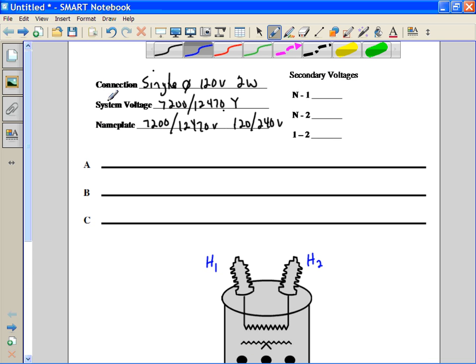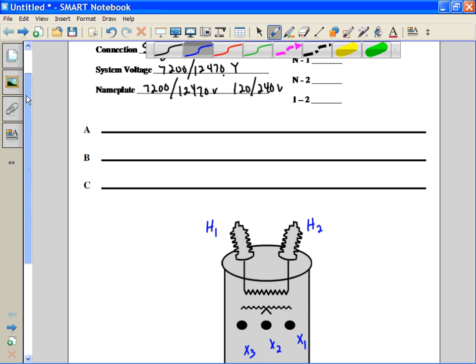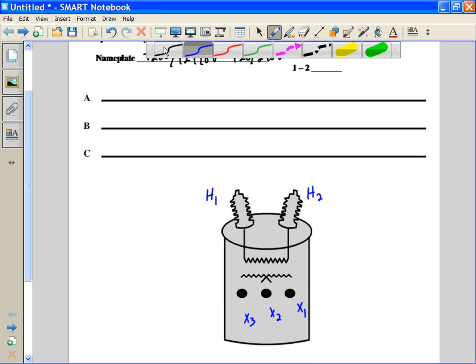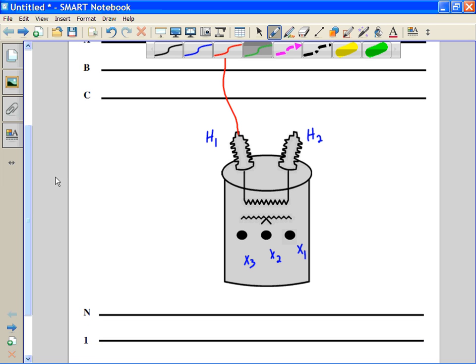So it's a Y connection on the primary. And we will just pick a phase wire. It doesn't matter which phase wire we pick on this. And I'll connect a phase wire to H1. And then since it's a Y connection, it's going to be a phase to ground connection or phase to neutral connection. We'll take the H2 bushing down to neutral.